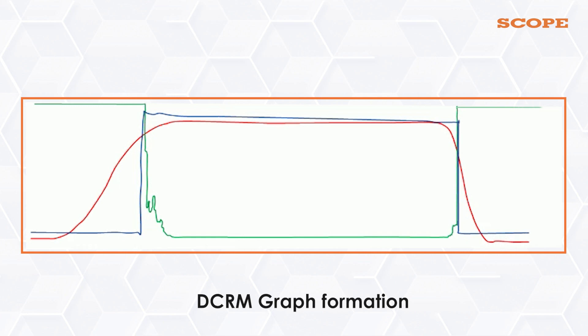For meaningful and in-depth analysis of the DCRM signature, it is recommended to have the travel curve of the circuit breaker along with the DCRM curve.